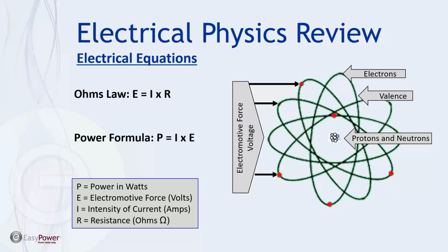So when we start talking about ratings of different pieces of electrical infrastructure, we're going to talk about parts where we want current to flow very well, which is the metal parts, and we want good contact, and parts where we don't want current to flow, and that's the insulated parts, the plastics, the ceramics, the glass, that will prevent the current from flowing from one part to another. As we start getting into fault current ratings and things like that, this is an important factor as to what kind of insulation levels you have between phases and between phase to ground. So that's kind of giving us a heads up here.